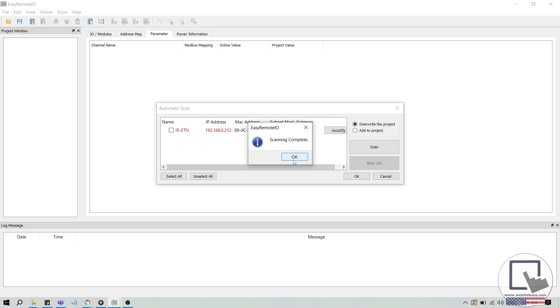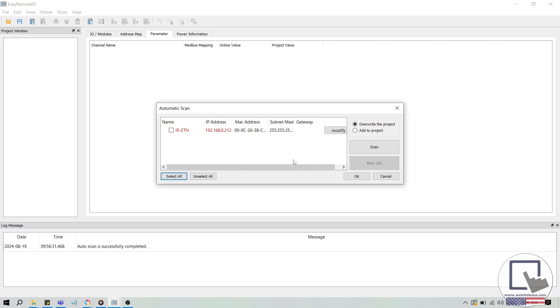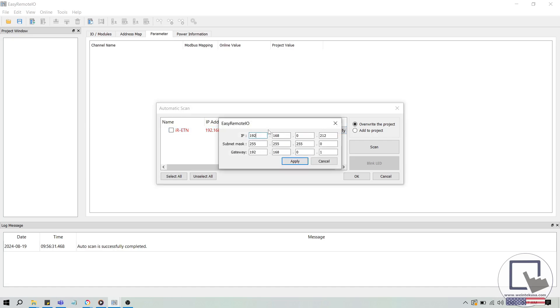In some cases, Easy Remote I.O. may find your device, but the IP address will be shown in red. This indicates that the IP address of the module is not on the same subnet as your computer, which may occur when you first start using the IR-ETN-40R as the default IP address is 192.168.0.212. In this scenario, you will need to modify the IR-ETN-40R's network settings using the Modify button before you can add this unit to your project.